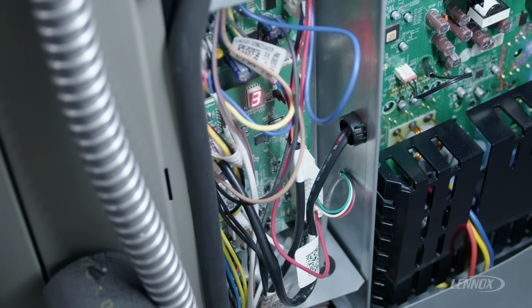To clear this error code, simply reset power at the same time, both indoor and outdoor, and bring it back on together to reestablish communication between the boards on the left and the inverter on the right.